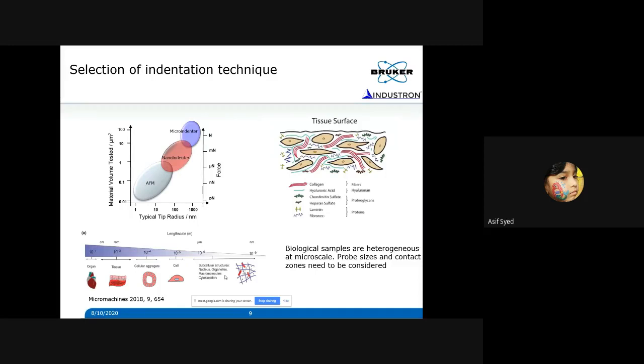So to cover the length scale, you need a certain type of instrument. Okay, with a Nanoindenter, we can go almost closer to AFM, like 10 nanometers or less than 10 nanometers, and we can go up to hundreds of microns in depth. We can do that with Nanoindenter. So choosing an instrument also depends upon the length scale at which you want to make the measurement. Normally with Nanoindenters, you can pretty much cover most of the length scales that are of interest with respect to biomaterials. But when it comes to DNA, if you want to sense DNA level forces to split the DNA and things like that, you probably end up using an atomic force microscope for that kind of application.